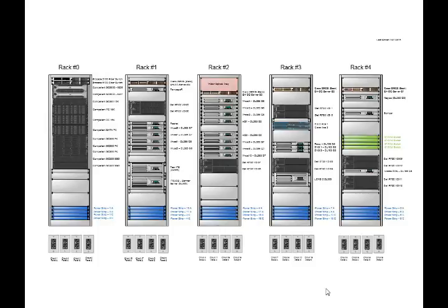And then the other redundancy coming out of the server is dual power. Dual power was kind of fun. It was a project that we updated less than a year ago now. But you'll see down at the bottom of your drawing there that there are 4 circuits at the bottom of each rack. Basically we have 2 different circuit panels in the server room. So 2 circuits are going to go to panel A, 2 circuits are going to go to panel C.